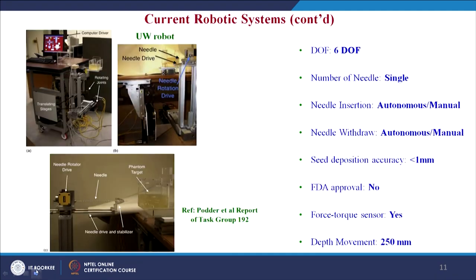Then comes the robotic system developed by the University of Wisconsin for automatic and semi-automatic radioactive source or seed placement. It has 6 degrees of freedom, involves a single needle, and supports both autonomous and manual needle insertion. Seed deposition accuracy is less than 1 mm. It is not FDA approved, is equipped with a force-torque sensor, and has a depth movement of 250 mm.